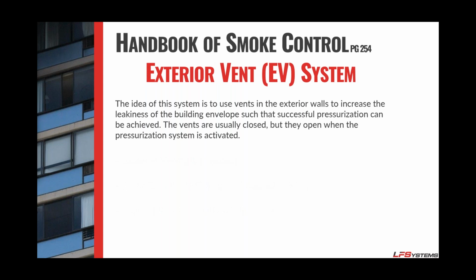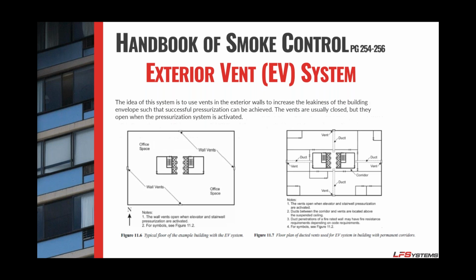Unfortunately, the EV system works exactly like a basic system with one exception. Instead of the building always being leaky, you build a tight construction building, and then in the event of a fire, you open some dampers and make the building leak. That's the general gist of the system. You'll have vents on the exterior walls. Sometimes you'll duct those to the elevator corridor. And in the event of a fire, all of those vents open, and it creates a natural draw into the building to create this leakage.